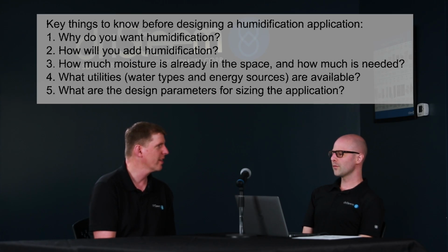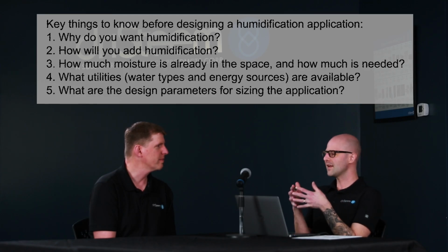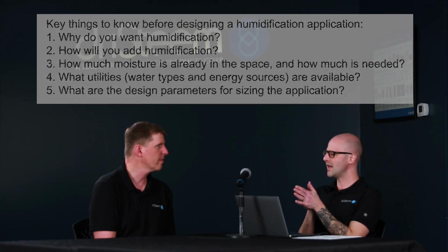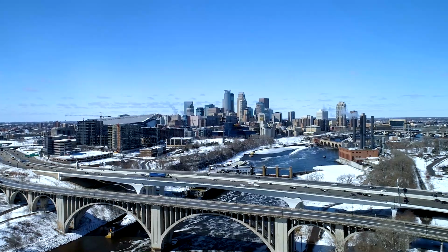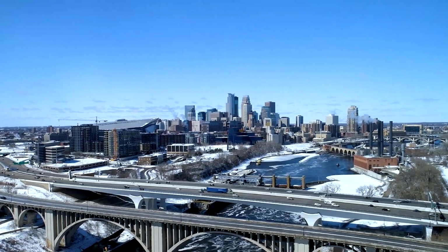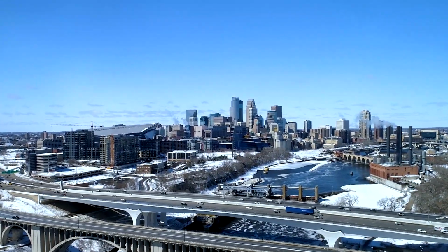Sure. So once I get all of that information, how do I end up then using that to determine my humidification requirement? Well, once you know, as an example, what your starting moisture content is, and that's often from ventilation. We need that in order to prevent our CO2 levels getting too high. And if we're in a cold climate such as Minneapolis, it's going to be cold and dry, and if we bring that in without conditioning it, it's going to actually dry out the space. So we need to add the moisture to it.